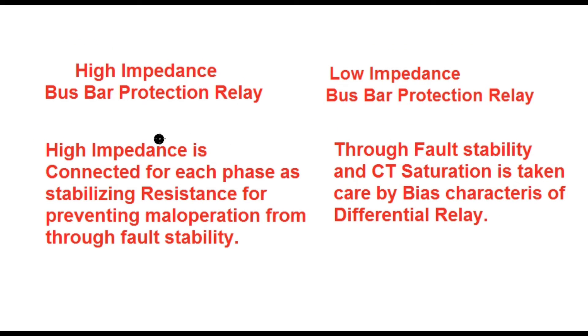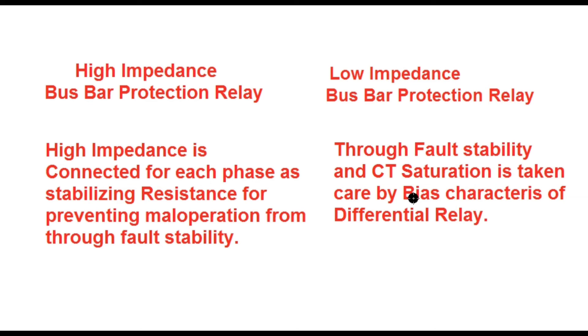In case of high impedance bus bar protection relay, a high impedance — called the stabilizing resistance — is connected in series with the relay for each phase. This stabilizing resistance is provided to prevent maloperation from through fault stability when either CT saturates. The maximum through fault current must be calculated to determine the stabilizing resistance. In case of low impedance bus bar protection relay, no such stabilizing resistance is required; through fault stability is maintained by the bias characteristics of the differential relay.